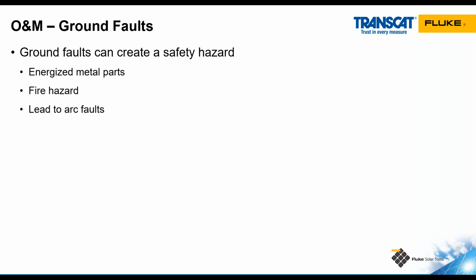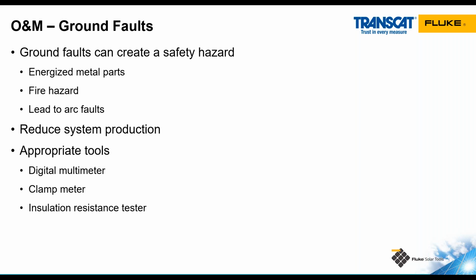Since there's current flowing to a non-current carrying metal part, I now have energized metal parts in the system that should not be energized. If it's arcing, where there's sparking across the connection, that sparking can cause fires. We see this often in ground-mounted systems where the sparks fall down into the grass and then the grass catches on fire. They will lead to arc faults as well, and they start out as arc faults and become solid ground faults over time.